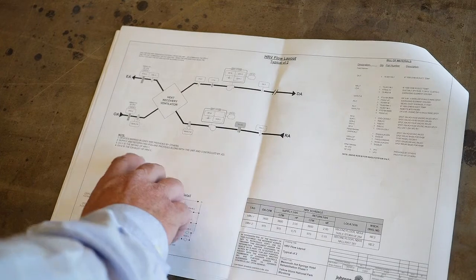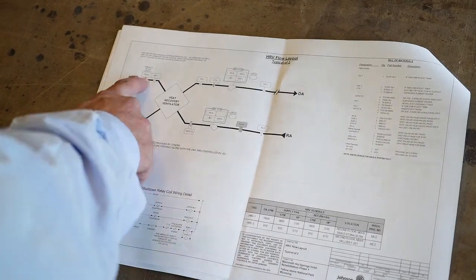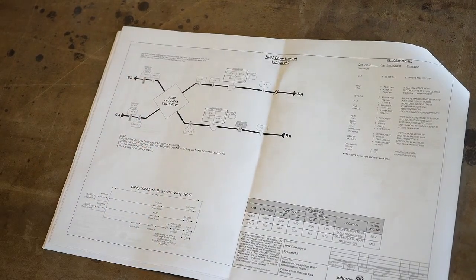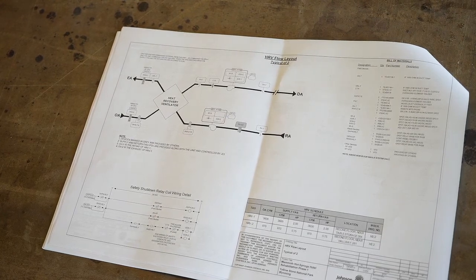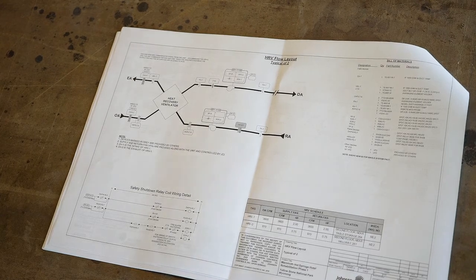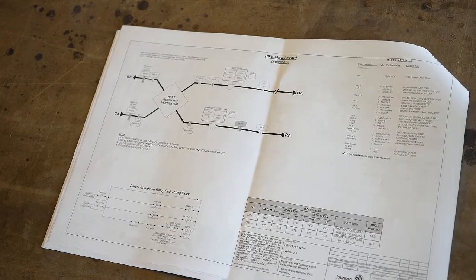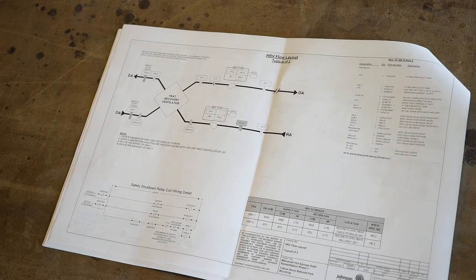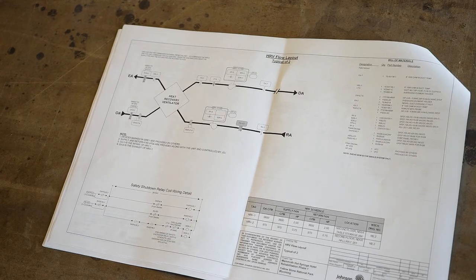So on the heat recovery units, there's an outside air damper and an exhaust air damper. It's important to remember that they're controlled internally from the unit. We're not controlling them. What we're doing is sending an enable to the HRV units. Once it's enabled, it commands both of those dampers open. When the dampers open all the way up, the end switches make, then they go back to their respective VFD drive, which is internal to the unit, and it allows the safety circuit to complete so that the drives can run.